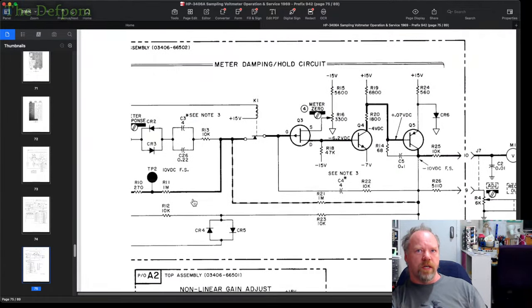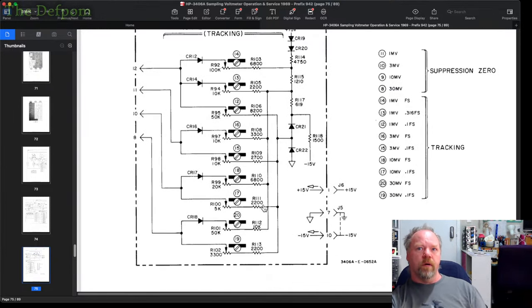The relay contact, yeah, that's a sample hold section. So what it does is sampling and holding. When you push the button on the probe, it will hold that current level on the meter, a bit like a max reading kind of thing. So when you're using the probe to test some circuitry, you can push that button, it'll hold it on the meter, then you can look away from what you're testing, pull the probe out, and look at the meter and see what that reading was. That's all that relay does, and that seems to be working fine, because I've been trying the button, and it's been relaying okay and the contacts seem okay. So I can't fault that part, at least not that particular function of that part.